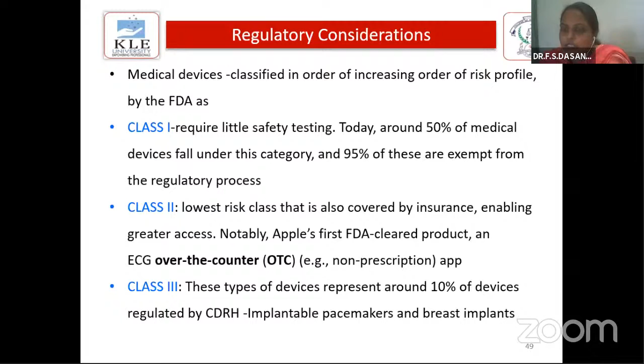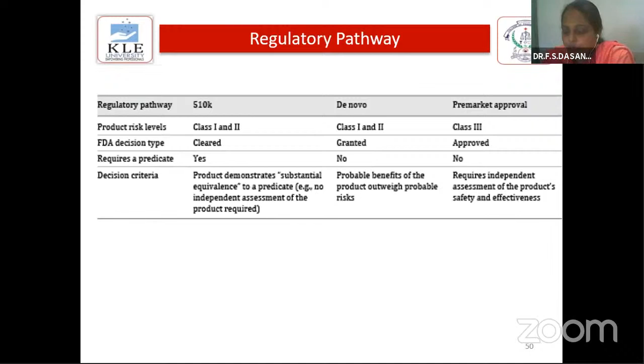So this is the regulatory pathway. For class 1 and class 2, the FDA decides. Yes, it can be cleared, but the product should demonstrate substantial equivalence to a predicate, the other products which are available in the market. And de novo means something new, as in class 1 and class 2, with probable benefits over the existing products, meaning it has more benefit than the existing product. Then the US FDA gives a de novo submission certification for that. And for class 3, you require pre-market approval, and it has to be approved, and it requires independent assessment of its safety and efficacy, as with any drug product which we are developing.